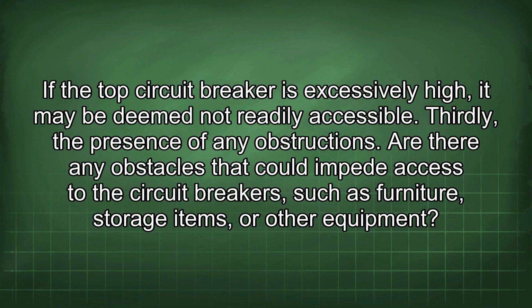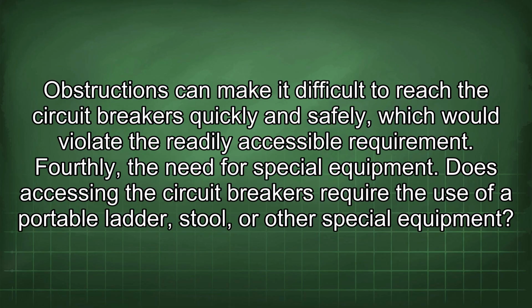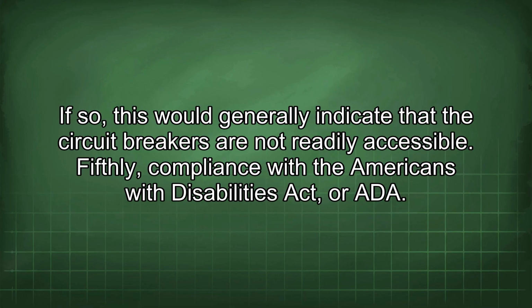Thirdly, the presence of any obstructions. Are there any obstacles that could impede access to the circuit breakers, such as furniture, storage items, or other equipment? Obstructions can make it difficult to reach the circuit breakers quickly and safely, which would violate the readily accessible requirement. Fourthly, the need for special equipment. Does accessing the circuit breakers require the use of a portable ladder, stool, or other special equipment? If so, this would generally indicate that the circuit breakers are not readily accessible.